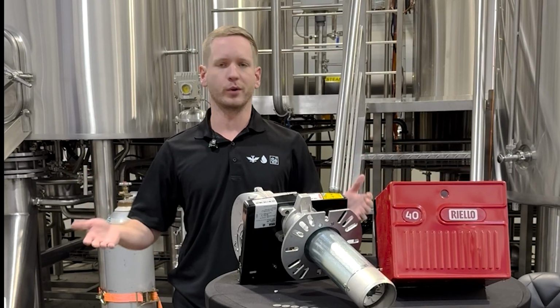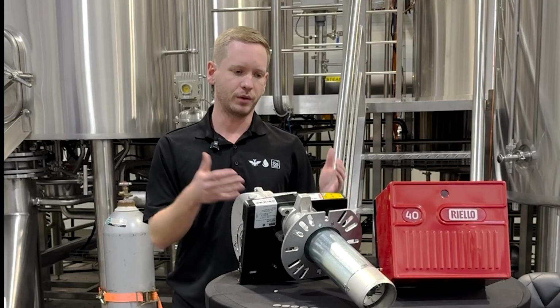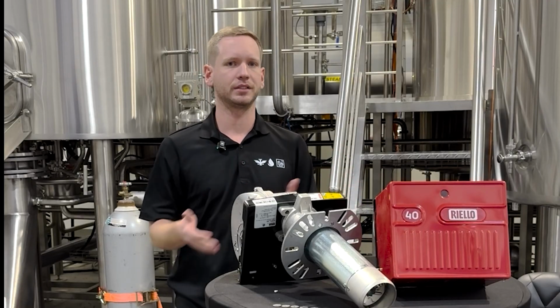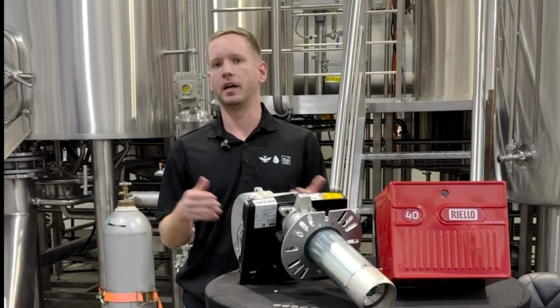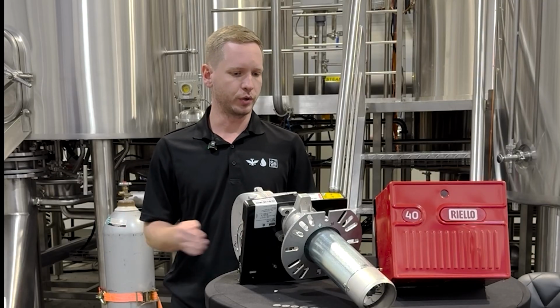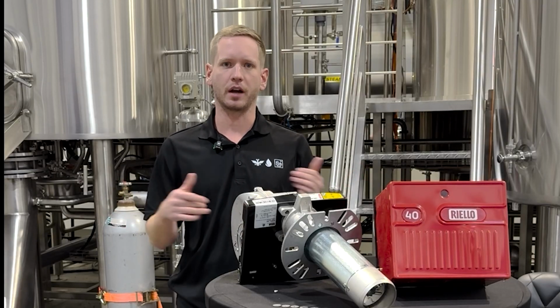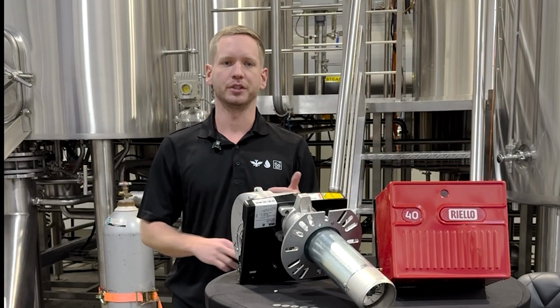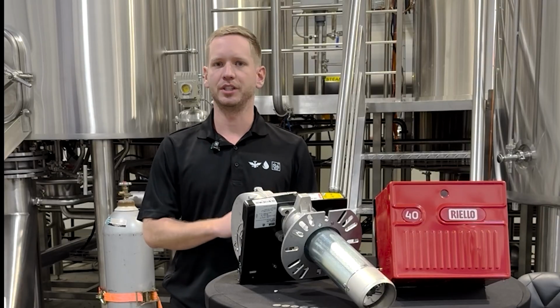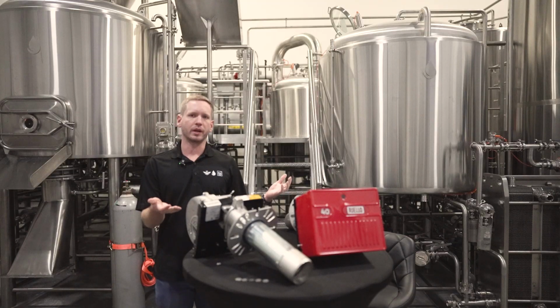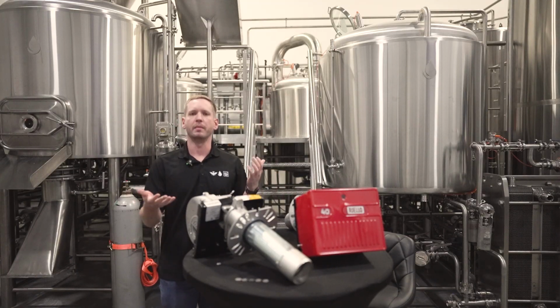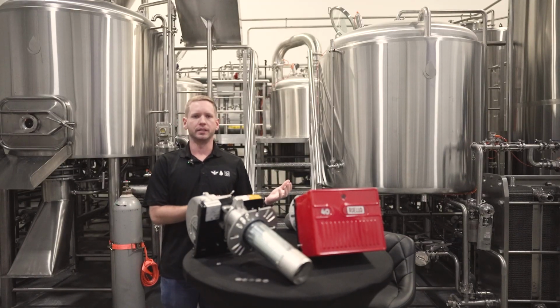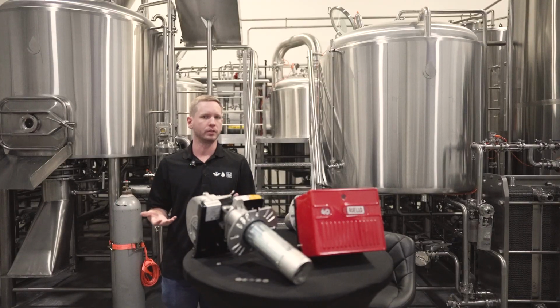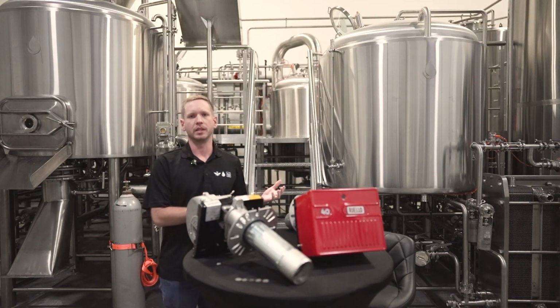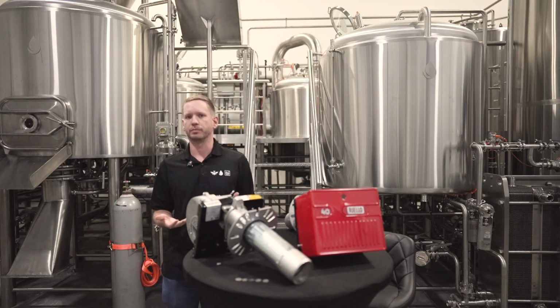Today we are talking Riello burners, their function, what they mean to your brew house, any necessary troubleshooting steps you might need, and proper maintenance procedures. We're going over all of this in depth, talking orifices, main header pressure, manifold pressure, ignition, ionization probes, all that stuff. Just our standard burners that we do on any direct fire system, their make, the models that we use, and some routine maintenance that you might want to consider when using and choosing a direct fire system from Deutsche Beverage Process.